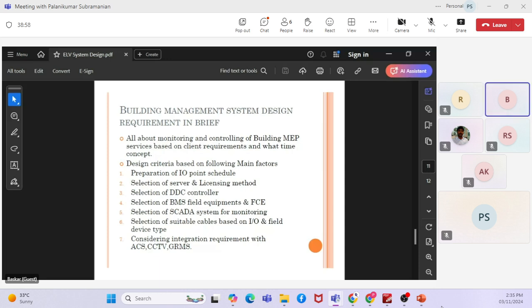What are the field devices? Let's say when we are talking about AHUs, the field devices are the humidity and temperature monitoring device, as well as the return air temperature monitor, outdoor temperature monitor, and the cooling coil temperature monitoring. So these are the parameters which are monitored by the field devices in the AHU.